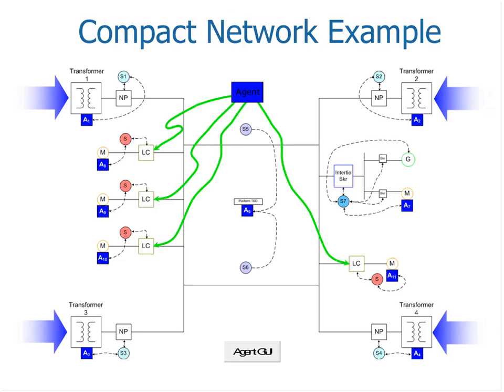We came up with 12 to 14 different use cases of what you could do if you had intelligence embedded into the actual monitoring and control system of the distribution system. What was unique was that there's nothing new about SCADA systems in utilities where you can monitor transformer temperatures in the utility control center, but there's nothing that coordinates that data with what's happening in the buildings. What we were trying to show is that agents could coordinate this, so distributed energy resources and the network itself can talk to each other and resolve problems in a way that makes the grid more reliable, and possibly also reduce electric demand in the building, which we worked on further later on the demand response side.